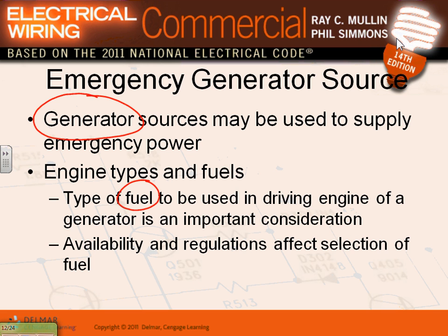Most of the time, guys, they have a 12, 24, or 48 gallon tank for the generator. Remember what Jerry was saying? 24 to 48 gallons is a good example for an emergency generator to have for driving the engine. Otherwise, you have a generator that doesn't have fuel for it. So what's that going to do for you?